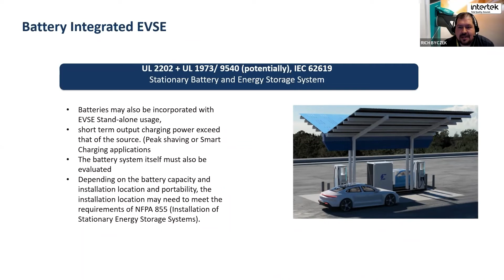UL 1973 or IEC 62619 are the core standards for evaluating the safety of larger scale stationary batteries. In the US, we have UL 9540 and its corollary test standard 9540A to evaluate the safety of that battery in its installation. Keep in mind there are additional regulations too—different building, fire, and electrical safety codes to be aware of. So there are additional masters to serve when adding large format lithium ion battery systems.